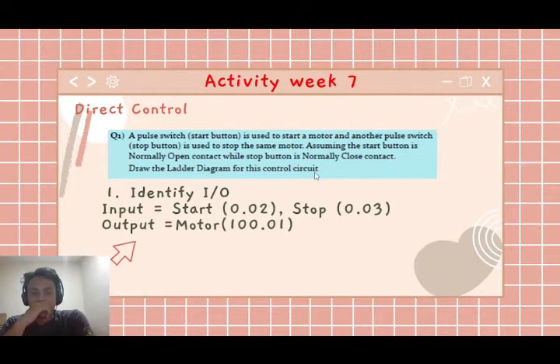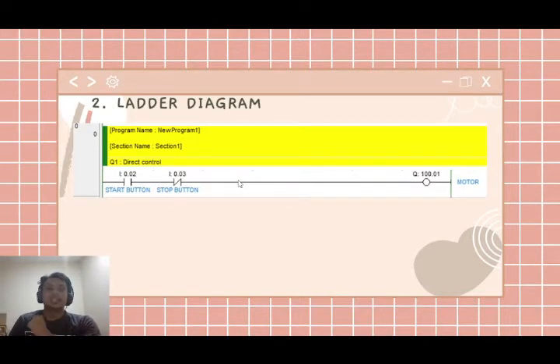First, we must identify the input and the output. We have 2 inputs and 1 output. Start button 0.02 is an input, the stop button 0.03 is an input, and the motor 100.01 is the output. This is the ladder diagram for direct control. The start button is a normally open contact, and the stop button is a normally closed contact.